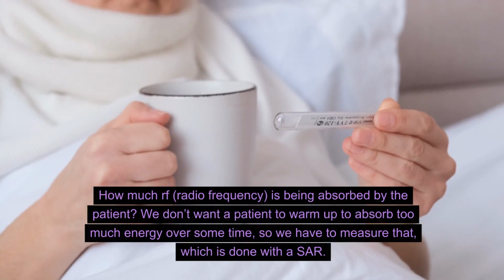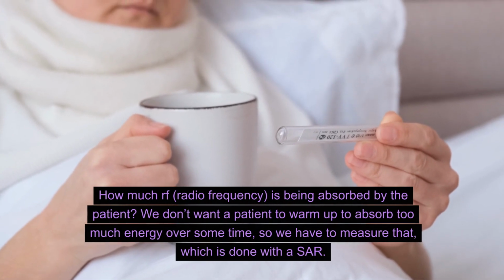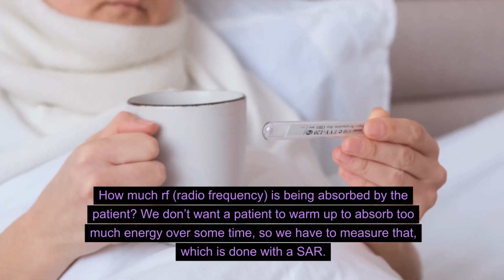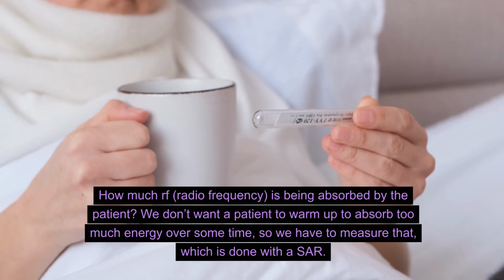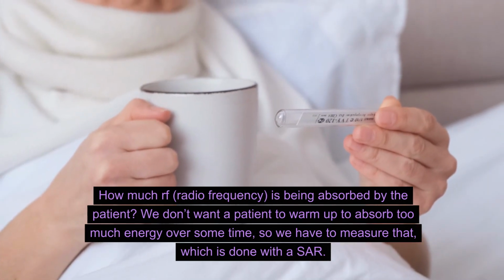Specific absorption rate: how much RF, radio frequency, is being absorbed by the patient? We don't want a patient to warm up by absorbing too much energy over some time, so we have to measure that, which is done with the SAR.